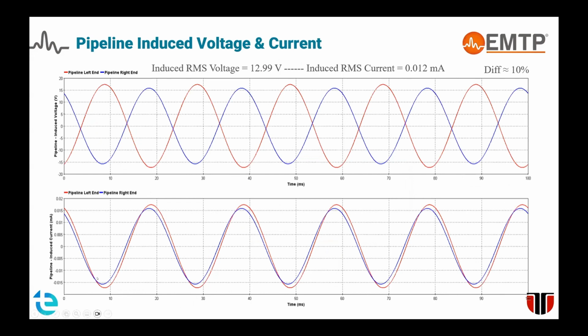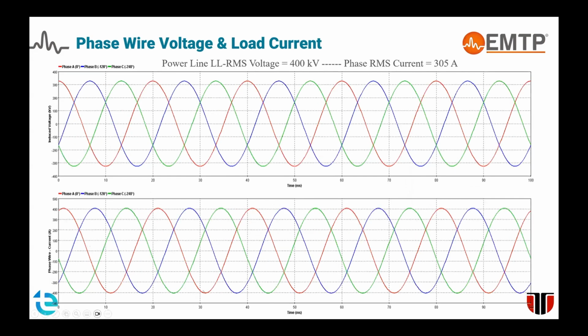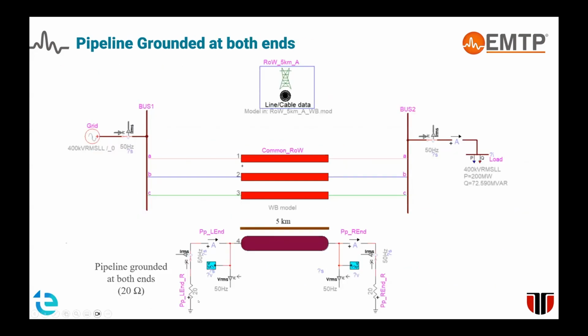Therefore, this kind of connection to a resistance could also be used to simulate and model insulation defects on the pipeline, to see what happens if the pipeline is not perfectly insulated, due to exploitation in time, holes appear in the insulation - what current will leave through that insulation fault, and how this could take place.